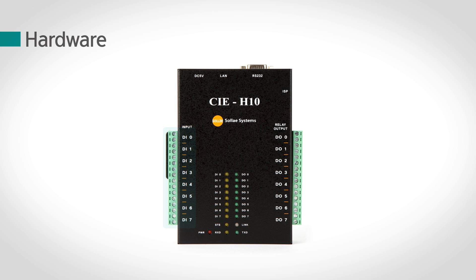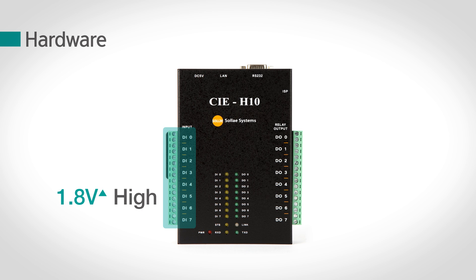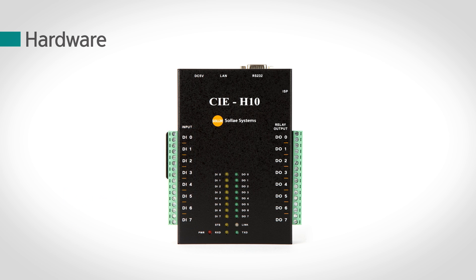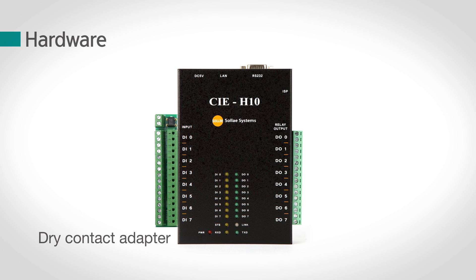There are 8 photocouplers for input ports. Higher than 1.8V is recognized as high and lower than 1.2V as low. To send a signal to a switch or relay, an additional dry contact adapter is required.